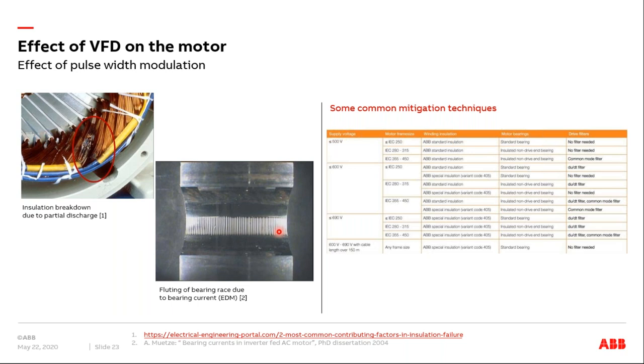We are aware of this, and we have different ways of solving these issues within ABB. As I said, it depends upon the size of the motor and how long the cable is from the drive to the motor. So how you mitigate is mostly case by case. And there are standards which mention that if you have a certain length of cable, you can use a certain method.